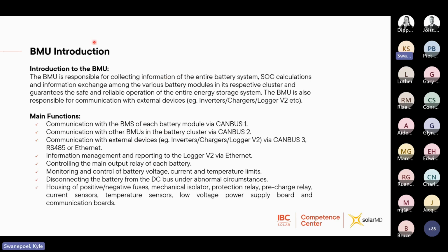And just to run through what the BMU does, or just a note on the BMS. So the BMS on the high voltage side will handle the same operation on the low voltage side. The only thing is it doesn't communicate CAN bus info to a BMU. The batteries communicate with each other. So the cluster is not formed to the BMU. The cluster is formed internally on the BMSs for the low voltage application. I'll explain what the cluster is shortly.